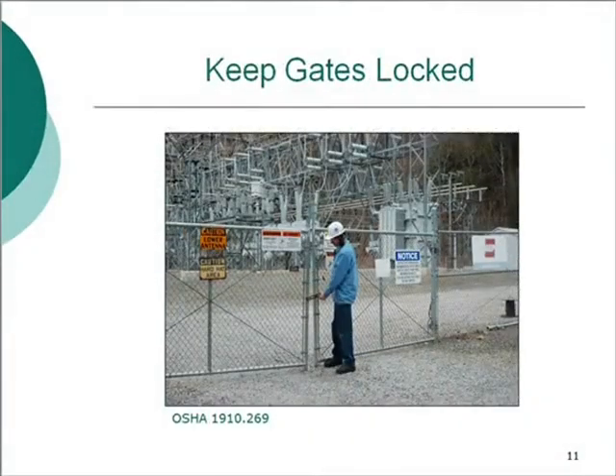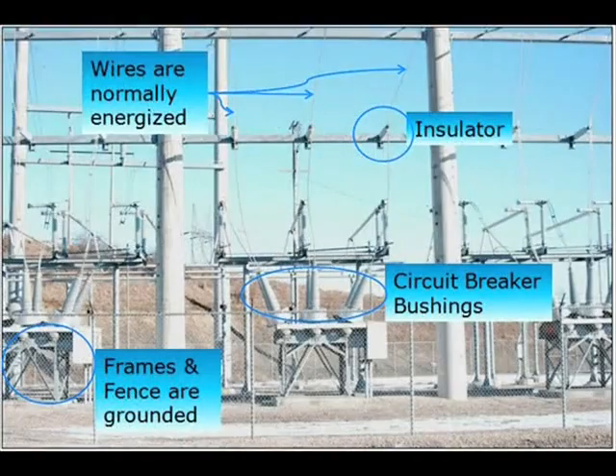When entering or exiting a substation, close and lock the gate behind you. Regulations require that entrance gates be kept closed or under the observation of an attendant at all times. This helps to prevent animals, children, and unauthorized persons from wandering into a hazardous area. Take a few minutes to look around the structures and try to distinguish between what is normally energized and what is not. Following these basic rules will keep you out of harm's way. Assume that the bus and conductors attached to the top of equipment are energized. Do not get near the wires, bushings, or insulators. By design, energized lines will be a safe distance away from the persons walking through the area.